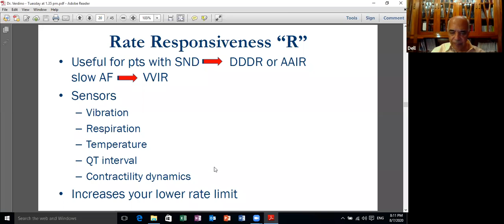So as a result of that, there are other forms of accelerating the heart rate, including respiration, by shooting a small amount of current to measure the impedance across the inflated lungs. If you get a decrease in the impedance, this increases the heart rate, or a temperature sensor. Some devices measure the QT interval and use it as a sensor. And some devices can calculate the amount of contractility around the pacemaker tip. All of these can sometimes be used in combination, which is more effective than using an isolated parameter in order to increase the heart rate. Which heart rate is increased by this? The lower rate limit.